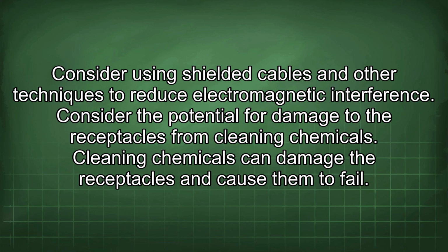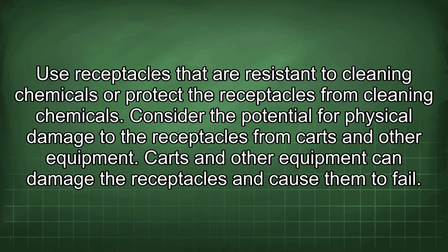Consider the potential for damage to the receptacles from cleaning chemicals. Cleaning chemicals can damage the receptacles and cause them to fail. Use receptacles that are resistant to cleaning chemicals or protect the receptacles from cleaning chemicals.